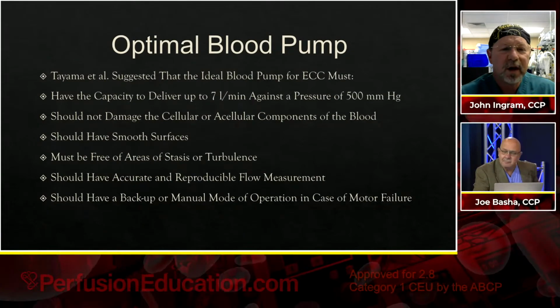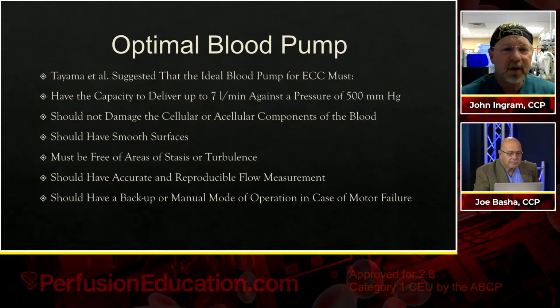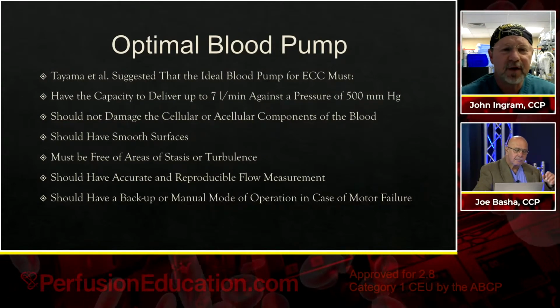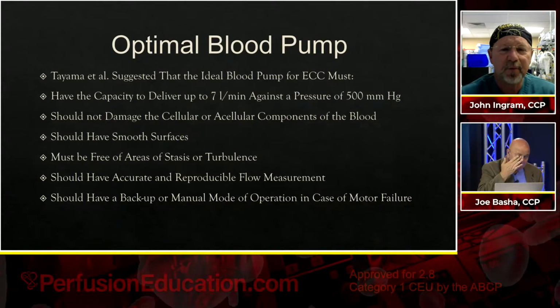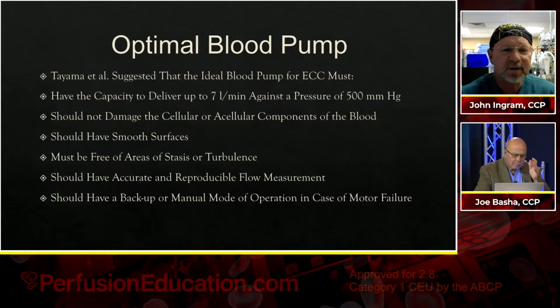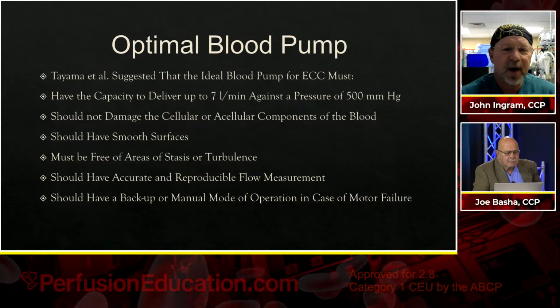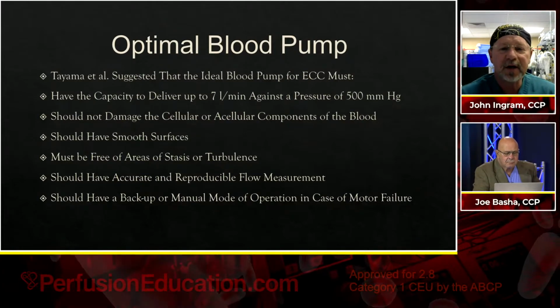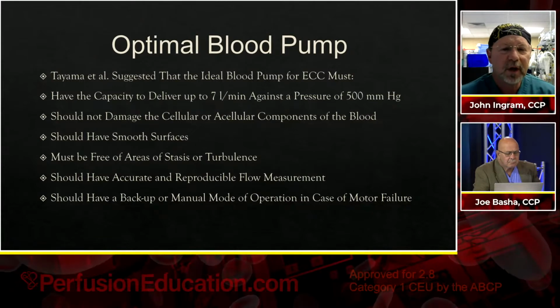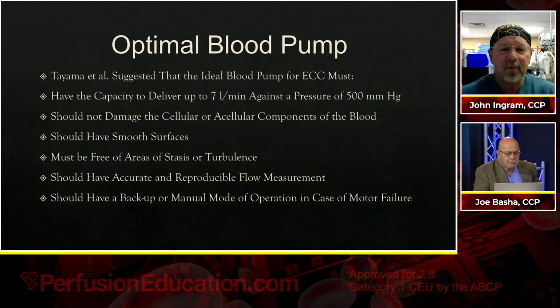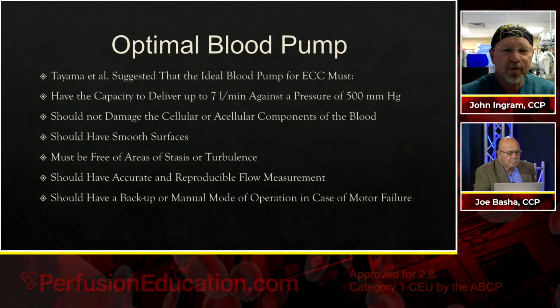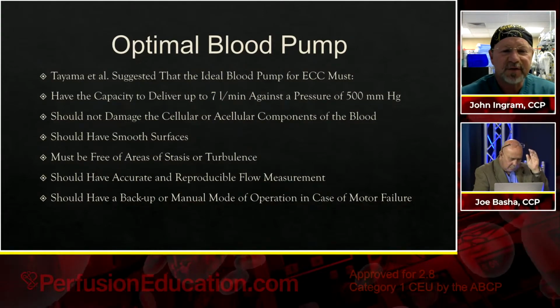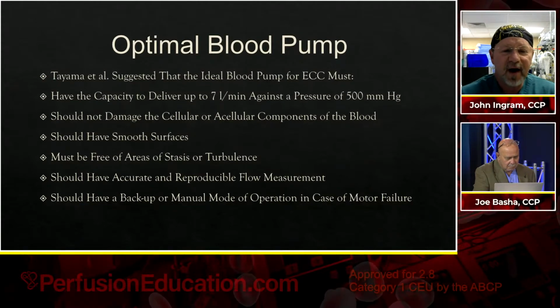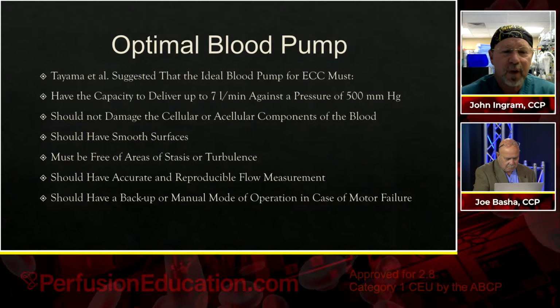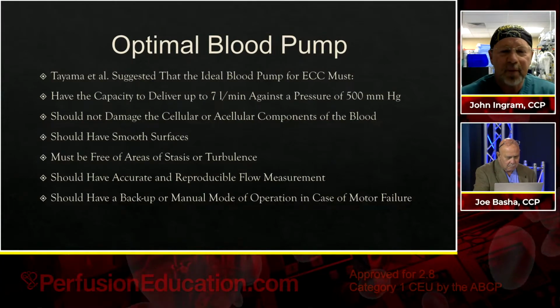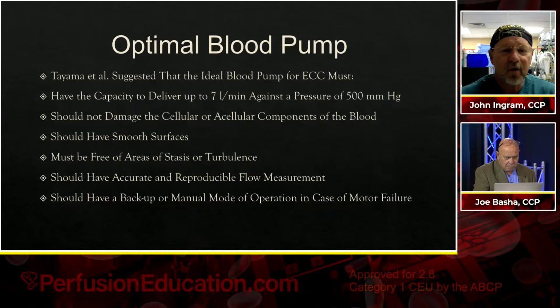And so what would be the optimal blood pump? Dr. Tayama, back about 10 years ago, suggested that the ideal blood pump for extracorporeal circulation must have the following features. It must have the capacity to deliver up to 7 liters a minute against a pressure of 500 millimeters of mercury. It should not damage the cellular or acellular components of the blood. It should have smooth surfaces. It must be free of areas of stasis or turbulence. It should have accurate and reproducible flow measurement. And you should have a backup or manual mode of operation in case of catastrophic failure of the pump.